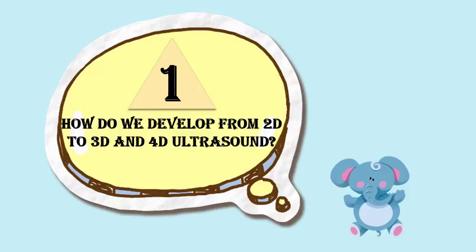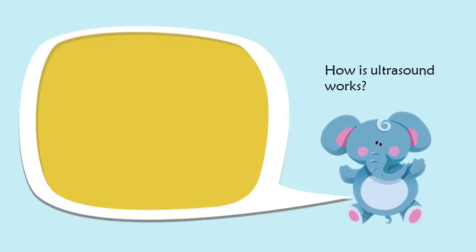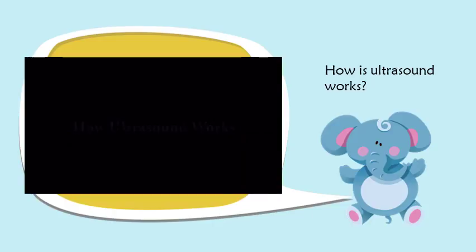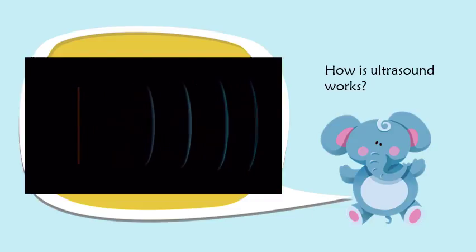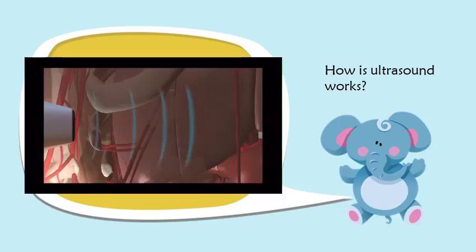How do we develop from 2D to 3D and eventually 4D ultrasound? Sound waves produced by a piezoelectric transducer are emitted into our body, and once the type of tissue is changed, sound waves would be reflected as echoes. The transducer receives these echoes and turns them into electrical pulses, which are processed and transformed by an ultrasonic scanner to become digital images.